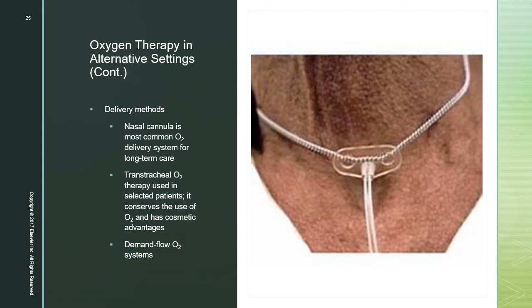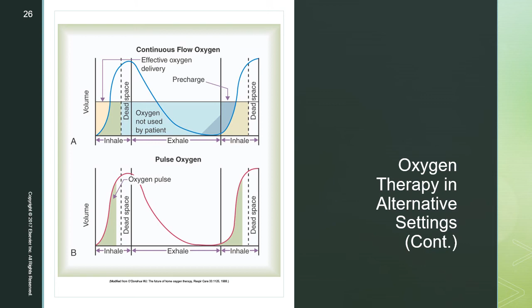This is a demand flow oxygen delivery. With continuous flow, most of the oxygen is delivered during the first half of the inhalation with the remainder wasted. But with a coordinated pulse, most of the oxygen is delivered during the first 25% of inspiration and no waste occurs.